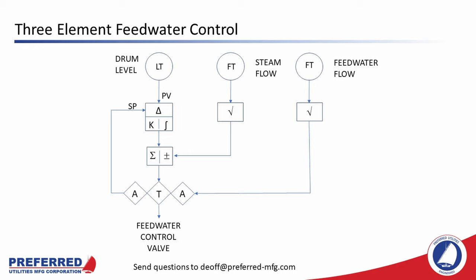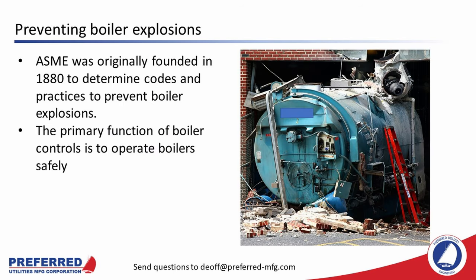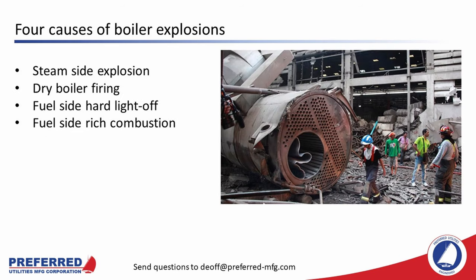Our final topic is preventing boiler explosions. Boiler explosions used to be a very big deal — they were very common. In fact, the American Society of Mechanical Engineers was originally founded in 1880 to determine codes and practices to prevent boiler explosions; their first meeting had 30 people in it. The primary function of boiler controls is to operate the boiler safely. Now that you know the basics of boiler controls, I'm going to illustrate how boiler controls are designed to prevent the most common causes of boiler explosions. All U.S. boiler and burner manufacturers strictly follow NFPA and other relevant codes — nobody in the U.S. makes an unsafe boiler or burner. Boiler explosions usually fall into one of these categories: a steam side explosion, dry boiler firing, fuel side hard light-off, or fuel side rich combustion.